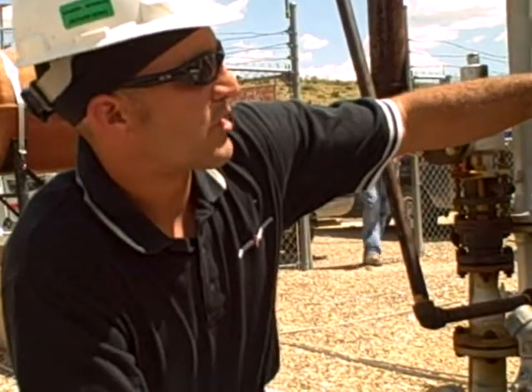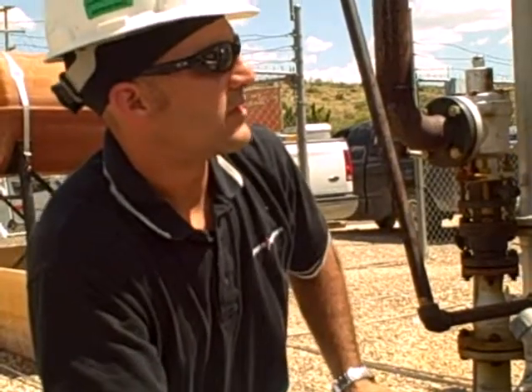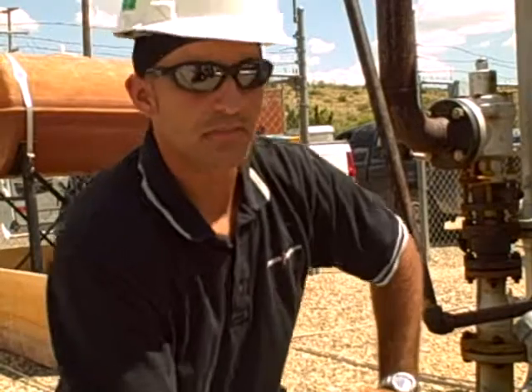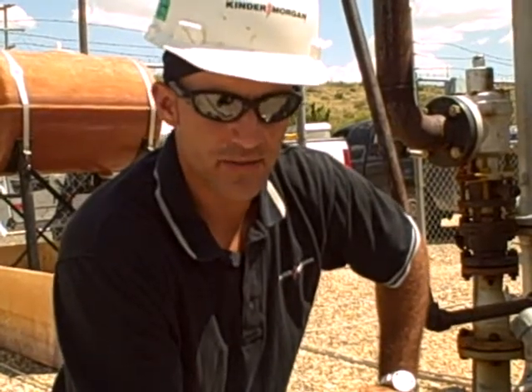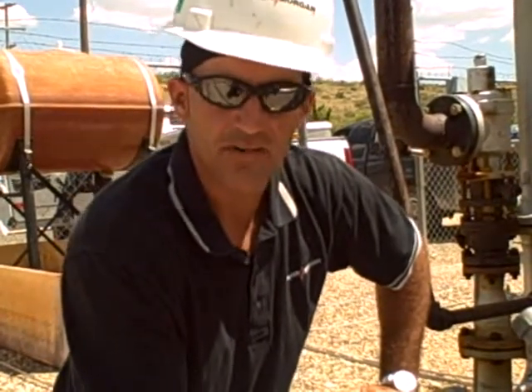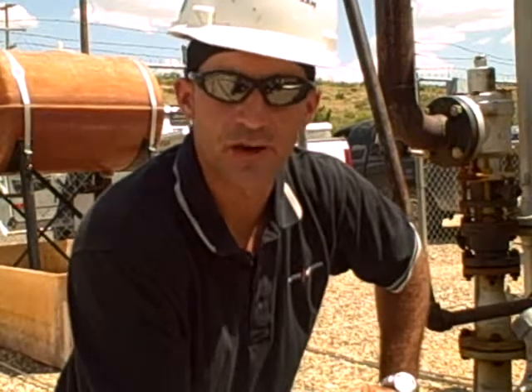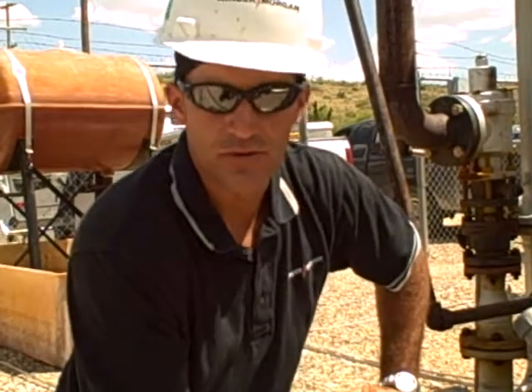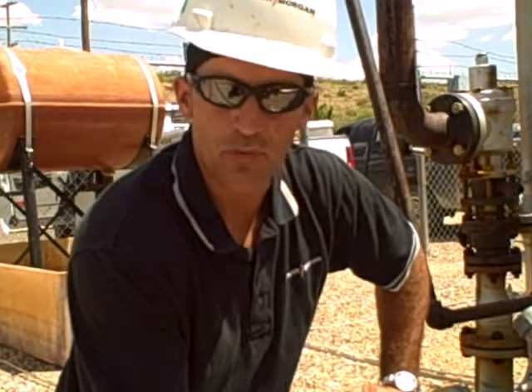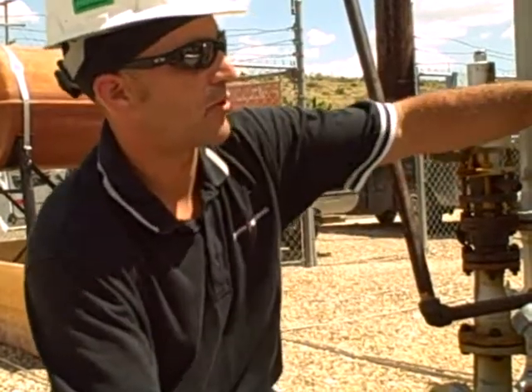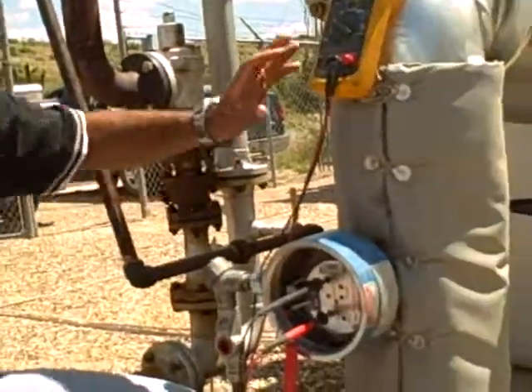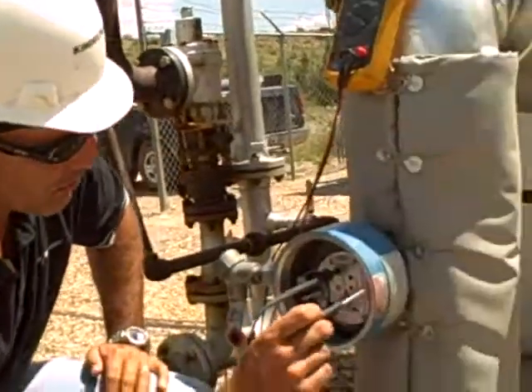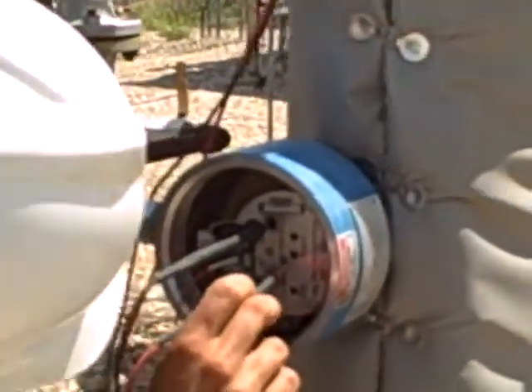I need to do a quick mathematical equation to get this calibrated. It's at 3% BS&W, so I need to take 3 times 5 units of measurements, which will be 0 to 5 volts. So I take 0.03, which is 3%, and it will be 0.15. So I need to set my lower range scale to 0.15, which right now it's at 0.16, so it's pretty close on, but we'll just go ahead and get it right on there.